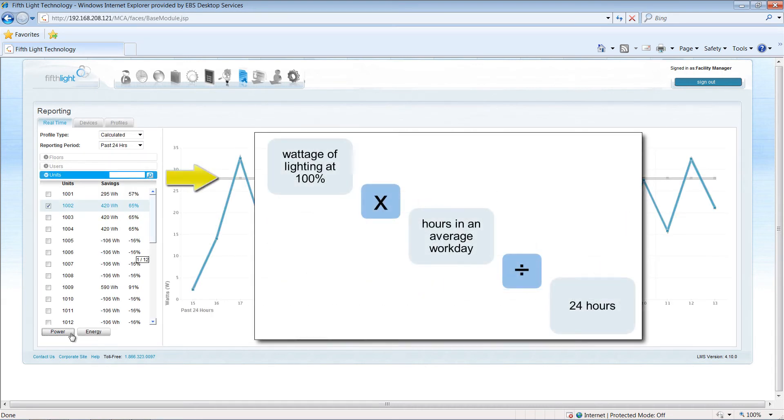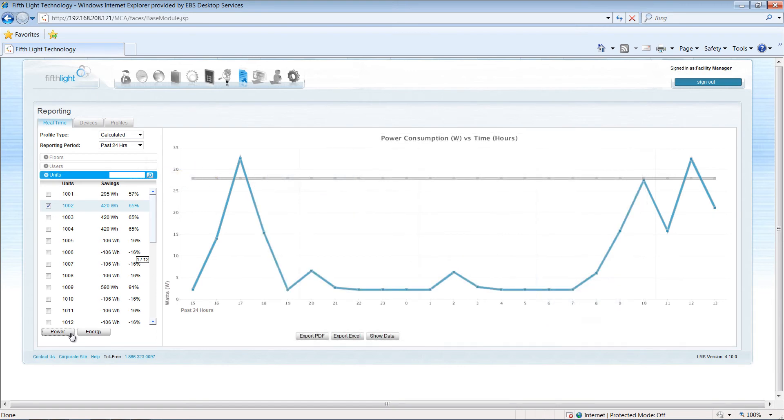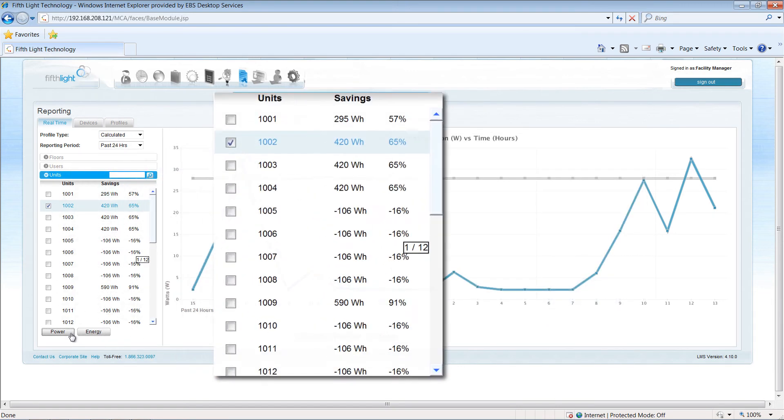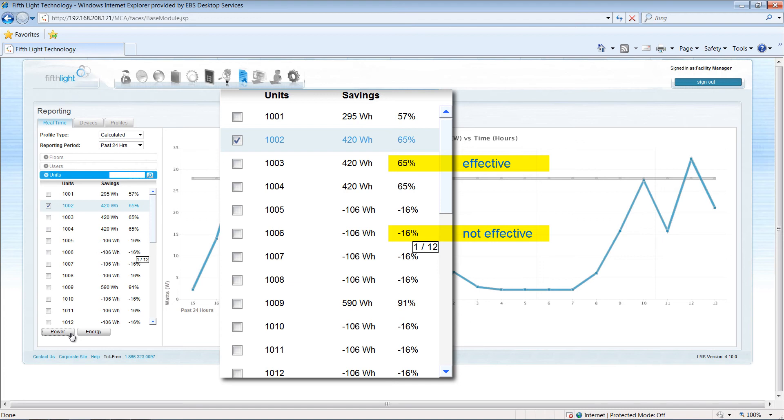The baseline is figured by calculating the wattage of the load being on full for the duration of an average workday, and then averaging this calculated wattage over a 24-hour period. Beyond the visual representation of the chart, percentage data helps to quickly determine the effectiveness of your strategies against the baseline. Watch your energy savings increase as you implement more stringent measures.